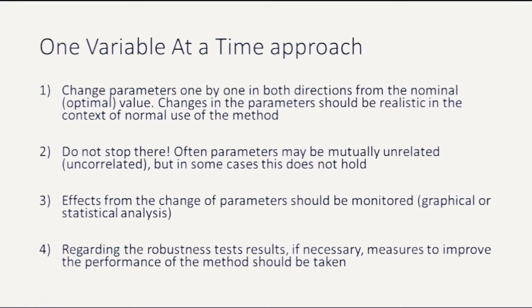Secondly, if you change something, do not stop there. Often parameters might be mutually unrelated or uncorrelated, but in some cases this does not hold. For example, change in mobile phase pH can decrease resolution between two adjacent peaks. Likewise, increase of mobile phase flow rate can also lead to the decrease of resolution. While separately any of these two changes can still lead to the loss of resolution, their occurrence together might lead to peak overlap.